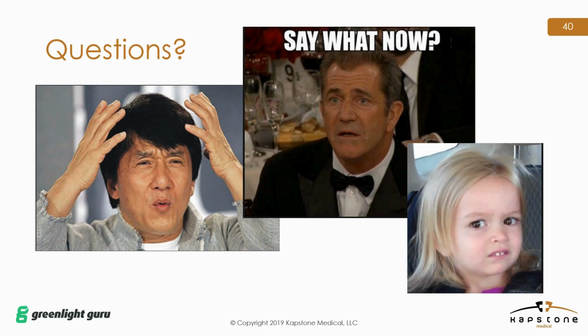All right. So for FDA, the QSR doesn't specifically talk about post-market surveillance. It talks about CAPAs, complaints, analyzing data, and things like that. But you're not looking at as wide a data source pool, or whatever you want to call it, as they're requiring in the EU MDR. So absolutely, you're trending already. Hopefully, you're trending when you're looking at your complaints and CAPAs and things like that. But you're not taking into account the broad performance of that device on the market.